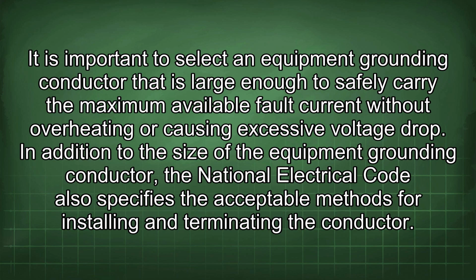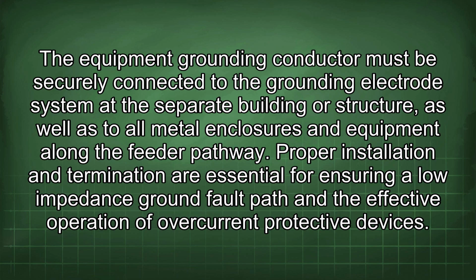In addition to the size of the equipment grounding conductor, the National Electrical Code also specifies the acceptable methods for installing and terminating the conductor. The equipment grounding conductor must be securely connected to the grounding electrode system at the separate building or structure, as well as to all metal enclosures and equipment along the feeder pathway. Proper installation and termination are essential for ensuring a low-impedance ground fault path and the effective operation of overcurrent protective devices.